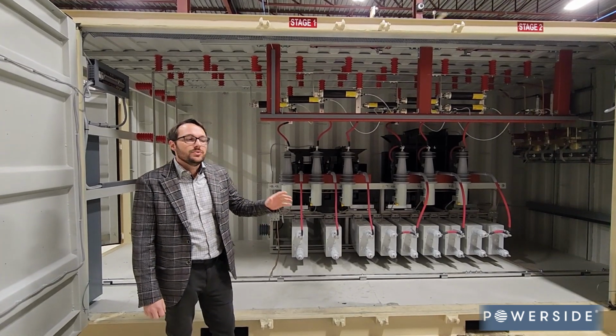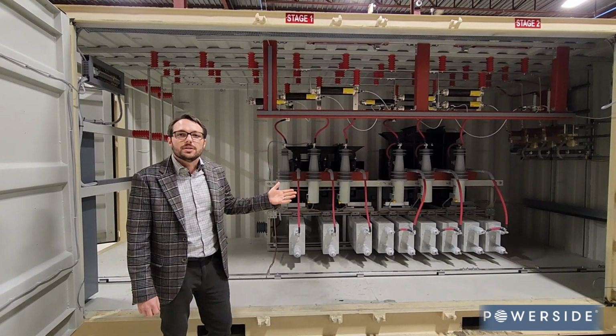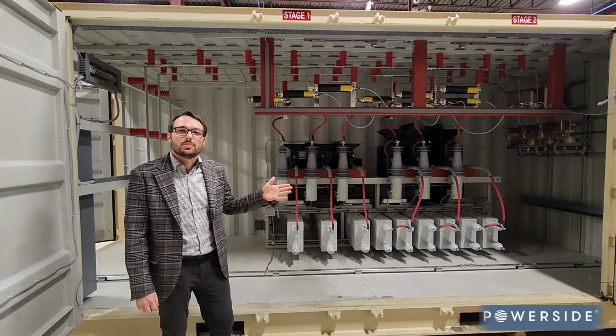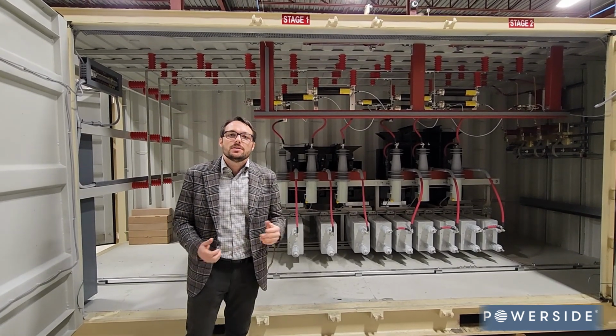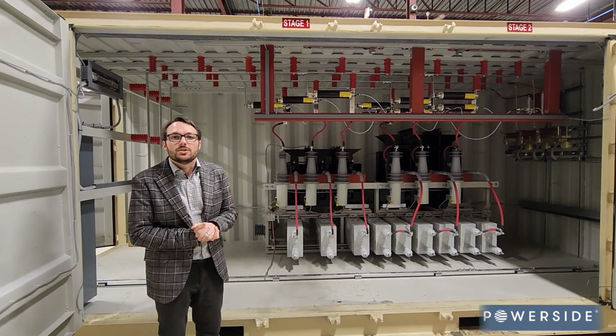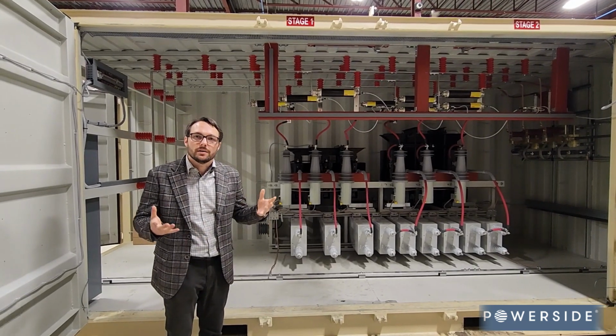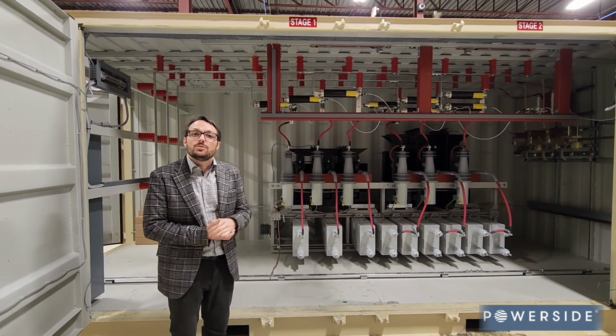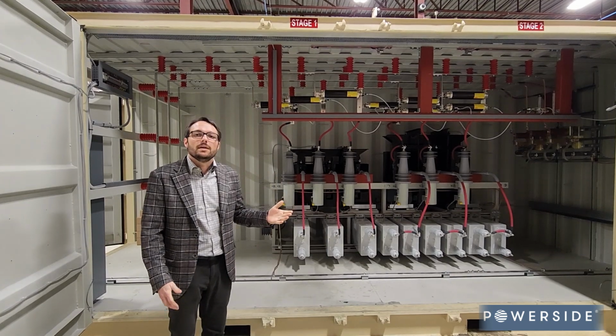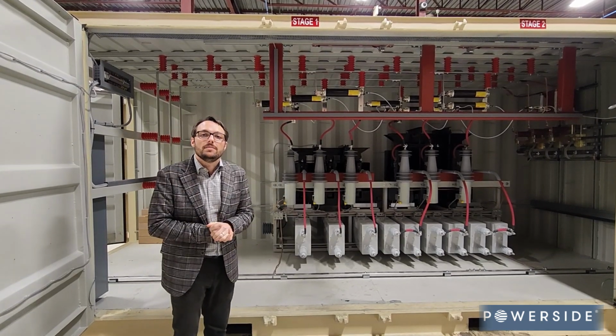Today I'd like to introduce a new configuration to our PowerMVar series product line. Our PowerMVar series product is our medium voltage reactive power compensation and harmonic filtering product, which we use from 2.4 kV up to 35 kV class.